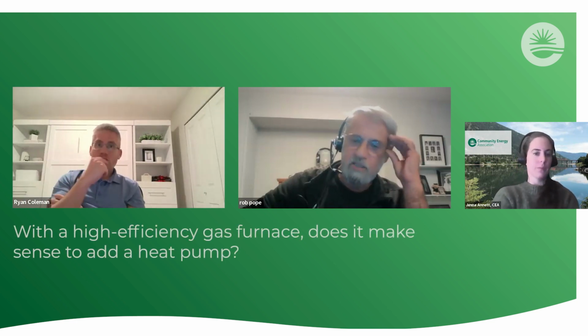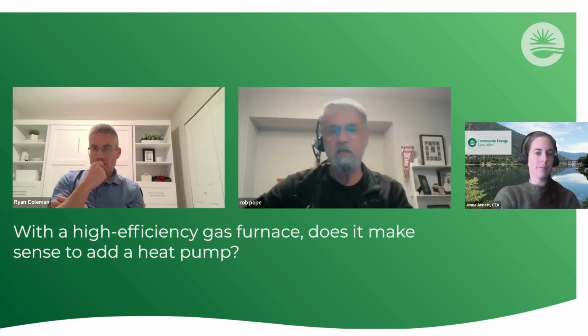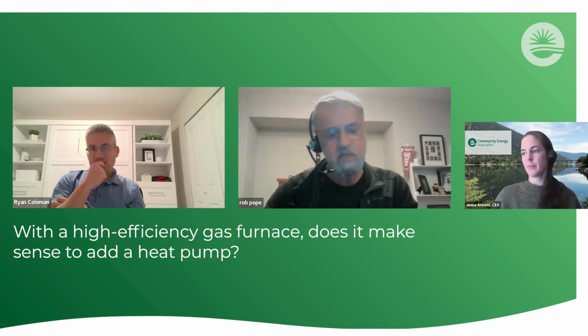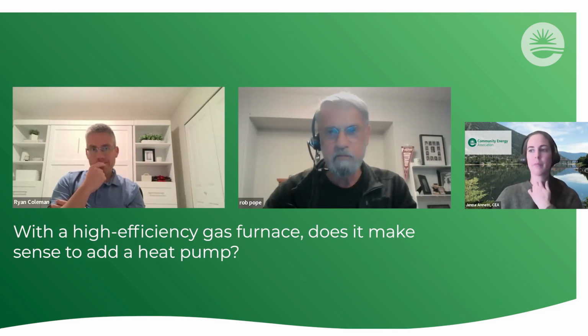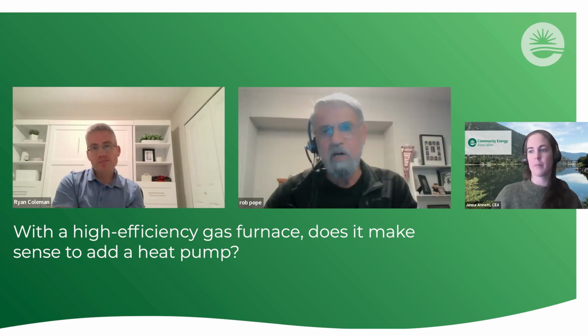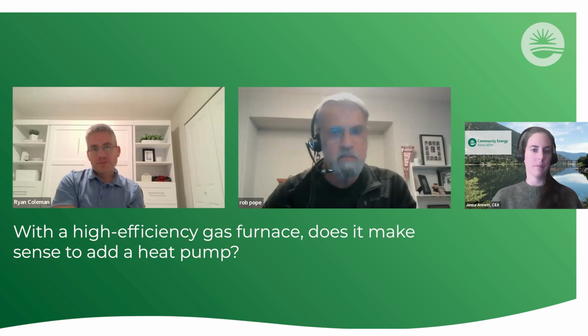All right. Celia says she has a 95% efficient gas furnace. Her house is well insulated. Does it make sense to add an air-to-air heat pump to her existing furnace with the purpose of reducing gas usage? That's a good question. If your gas furnace is 95% efficient, it's relatively new, it's doing a great job. The question then comes down to what could possibly motivate you to spend the money to put a heat pump? Maybe you want cooling.